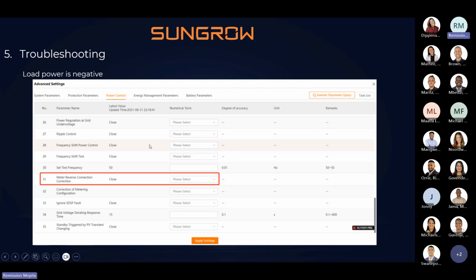And then we have one important feature in the settings, under power control, which is called meter reverse correction. We use this to correct the CT direction. If the client has connected the CT in reverse and the power in the house is constantly negative, we just enable the meter reverse connection correction to get a positive value on the load.